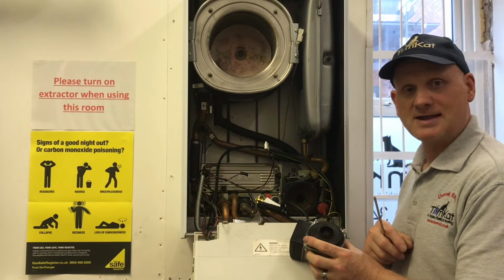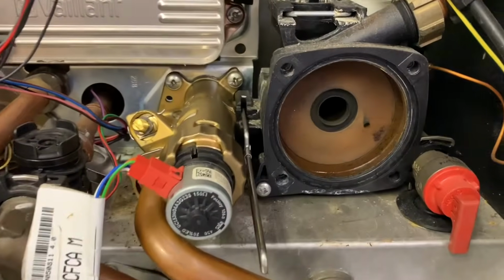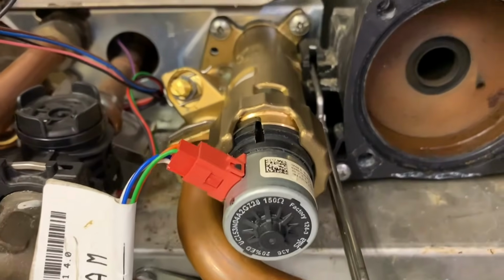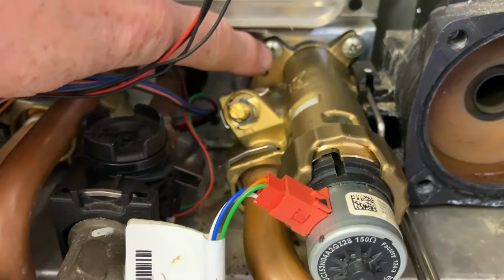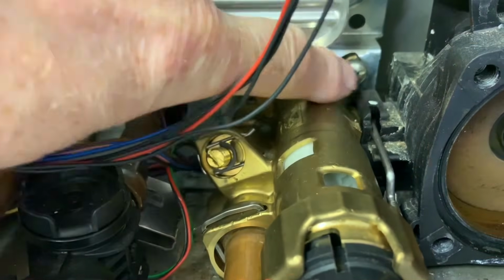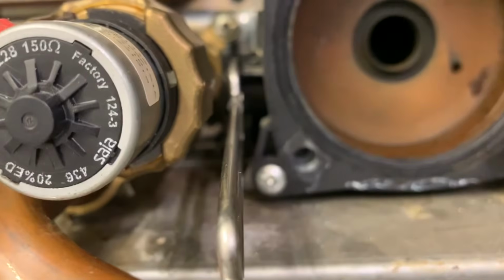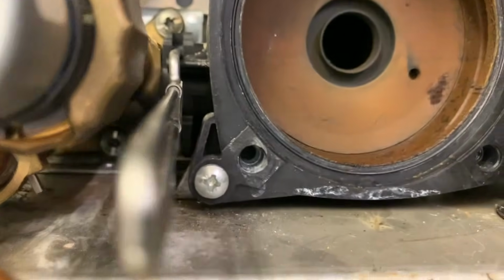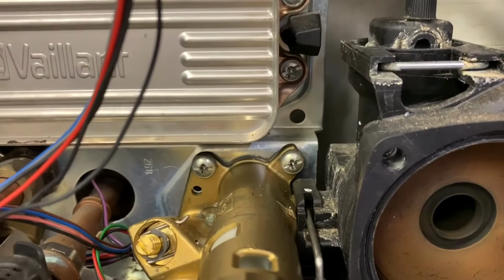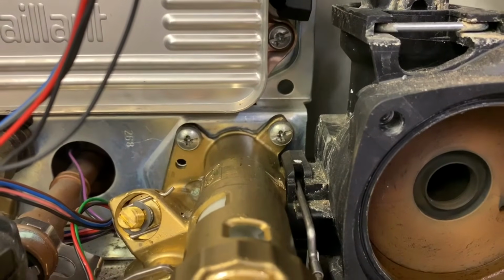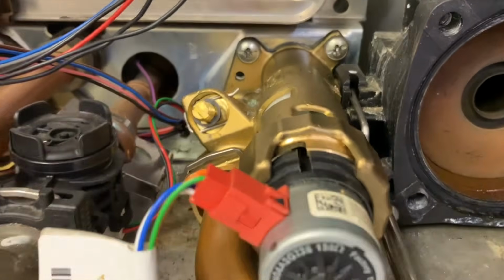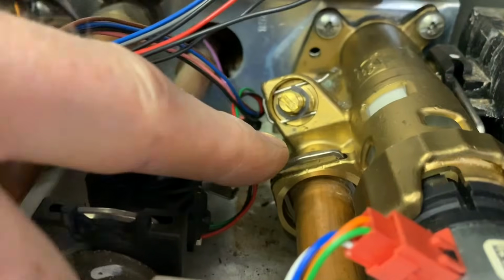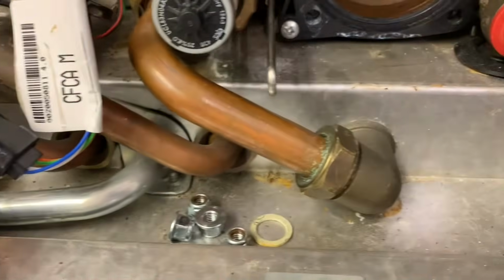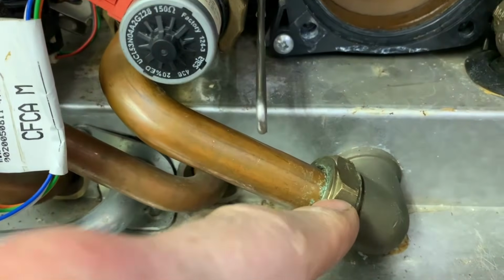Next thing we're going to look at is the diverter valve. Now the pump head's removed, we can see the diverter valve more closely. So the main thing we need to do with the diverter is remove that screw, and there is also an awkward screw underneath there somewhere, if you can see it. Just see it in the background. They actually got Phillips head screws or flat screws. Sometimes they can be seized, sometimes they can be dead easy to get off. Also, what we've got to do is remove this pin here, and we have to undo this nut here.